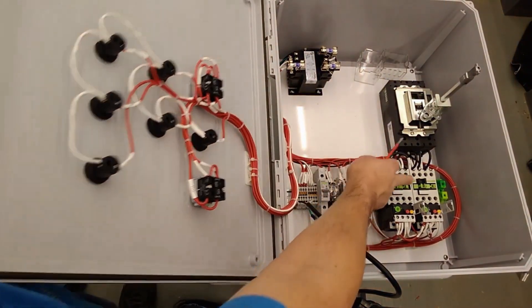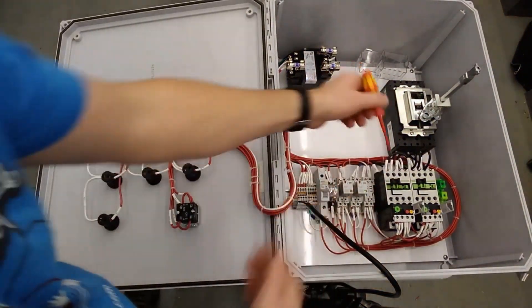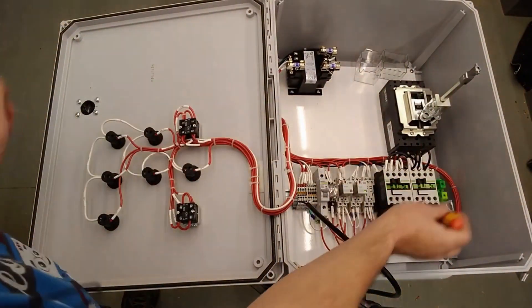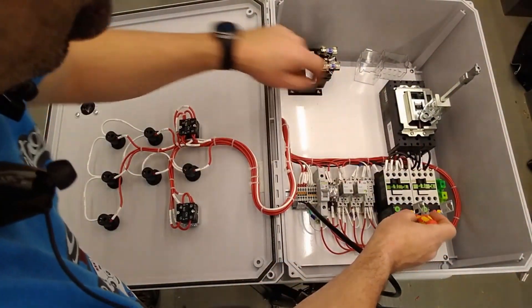You see we get the fan 1 running. You see the contactor is pulled in. Now I'm going to trip fan 1's overload and you'll see fan 2 come in.